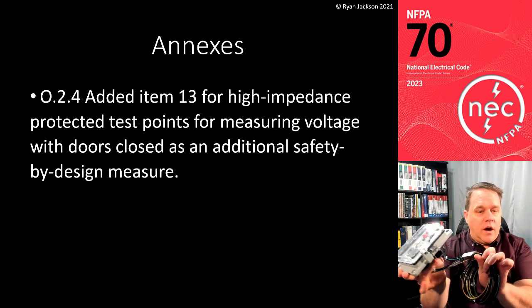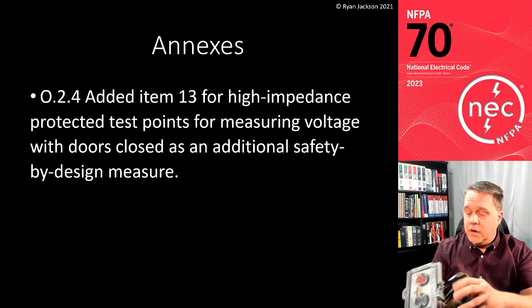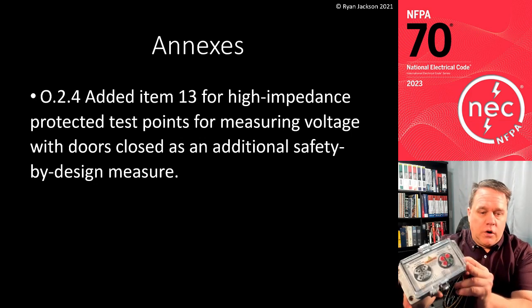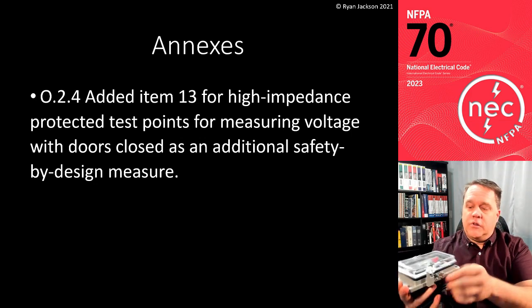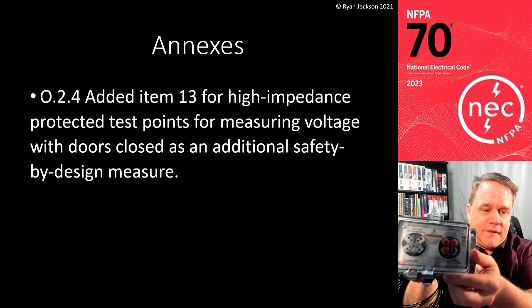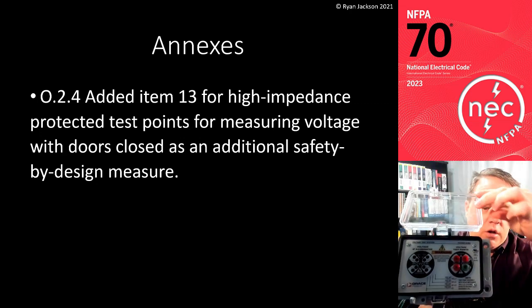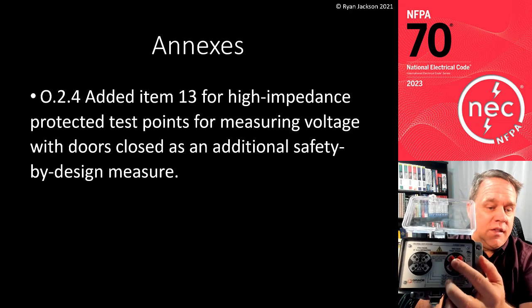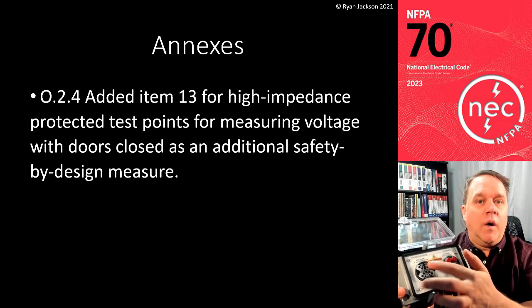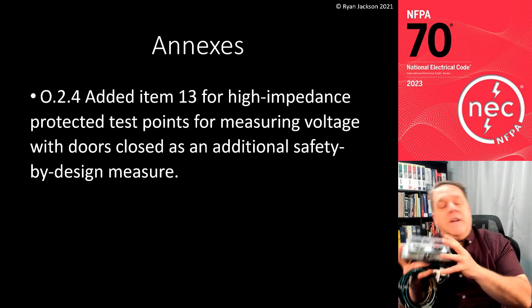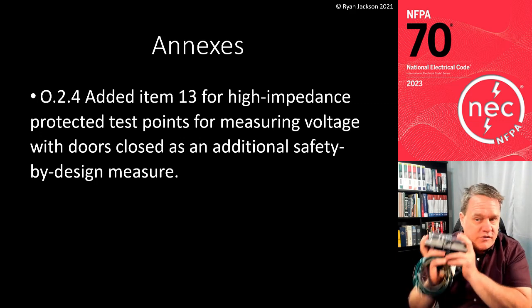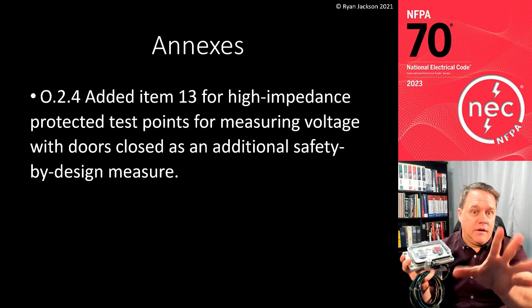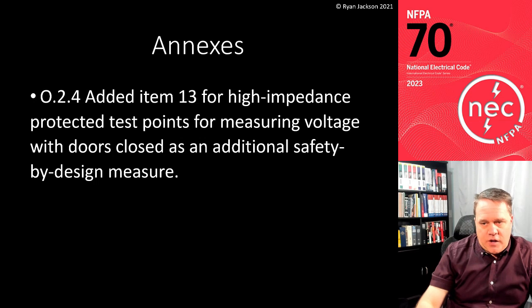So you wire this thing, it's permanently installed, right? So you install this on the door, you wire it into the equipment, and then when you want to test to verify the presence or absence of voltage, you can open it up, stick your test leads in there, and it will tell you what's happening with the equipment. Very, very nice option for safety by design, right? And now that was added in Annex O.